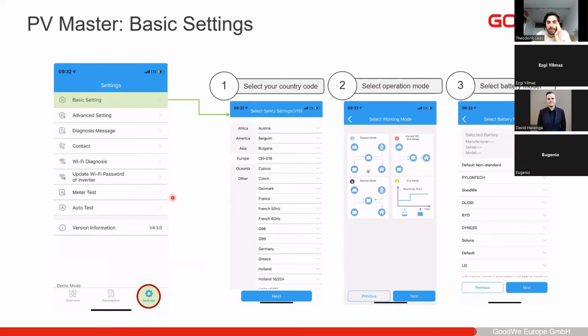The other settings here are in some cases good to set up as well. For example, if you want to limit the export power to the grid, you need to set that up afterwards, or if you have specific battery settings. But for the inverter to be up and running and producing energy, you only need to click on basic settings.